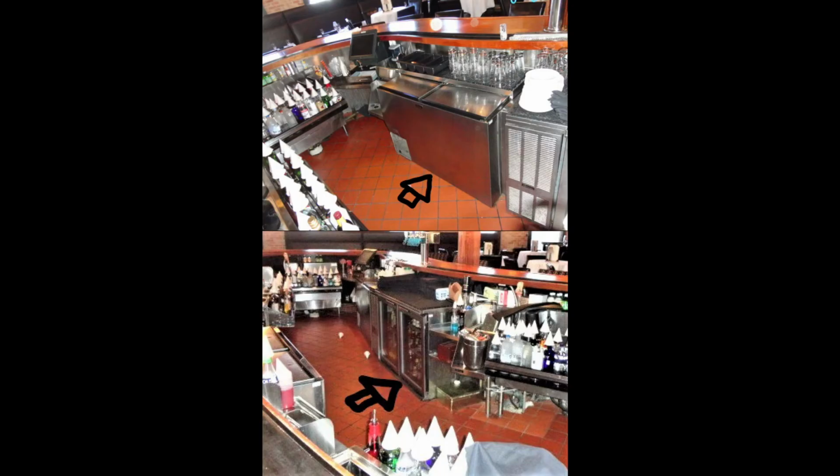Other problems often occur when you have equipment such as mug chillers and beer coolers that are top open, and they've taken the casters off the bottom to sit directly on the floor. And what happens is all the water on the floor gets underneath it and rusts away the bottom and gets into the insulation and really causes a lot of odors. And back again, to the fruit flies, the whole nine yards again.